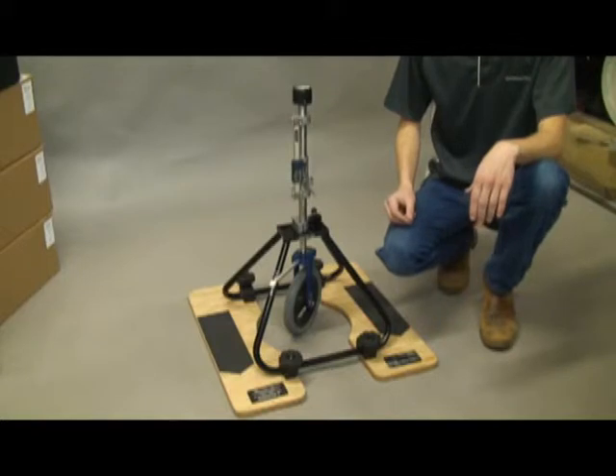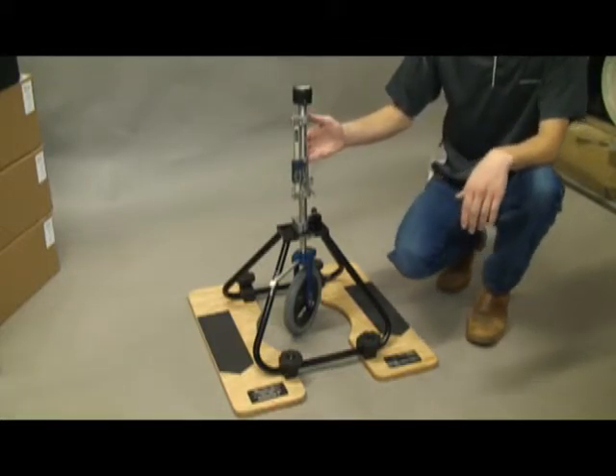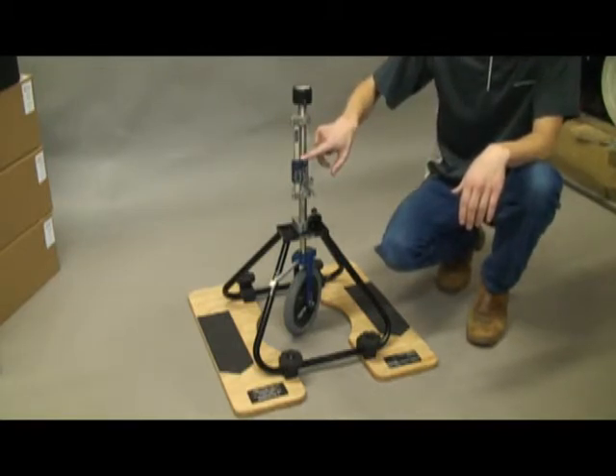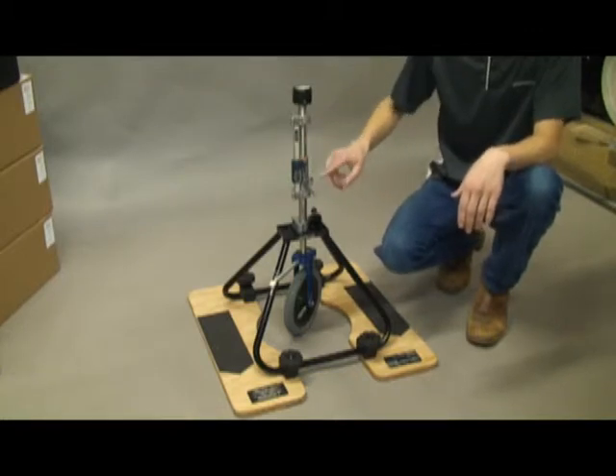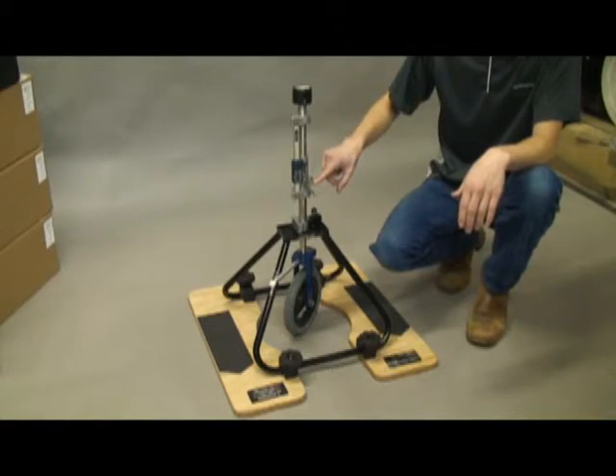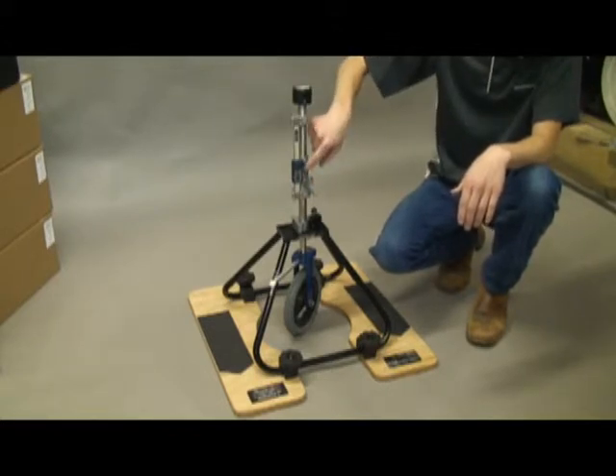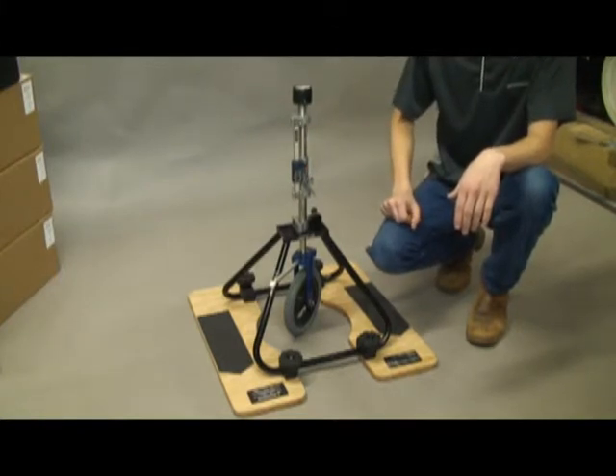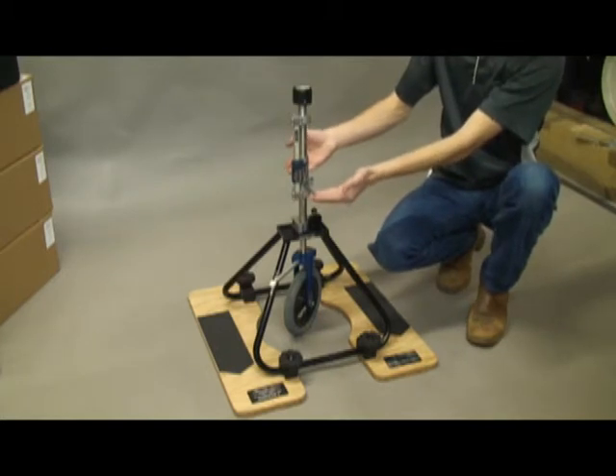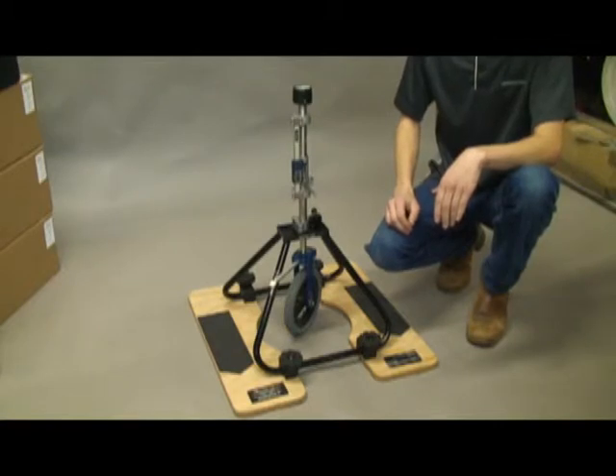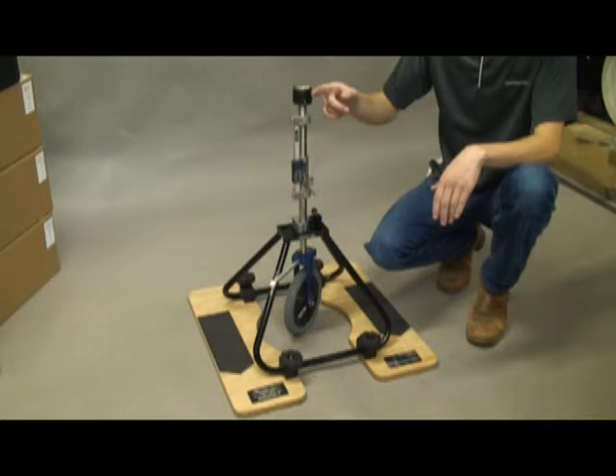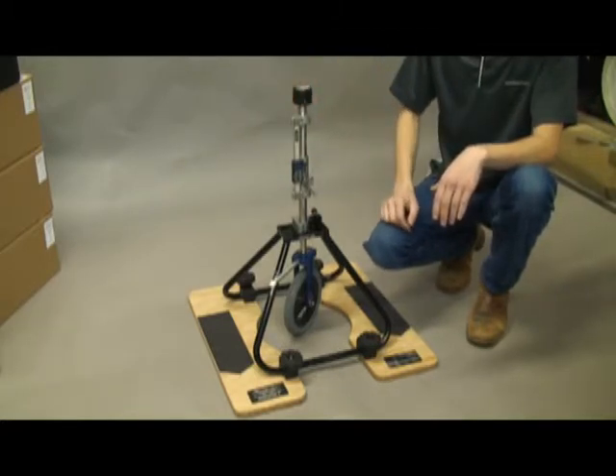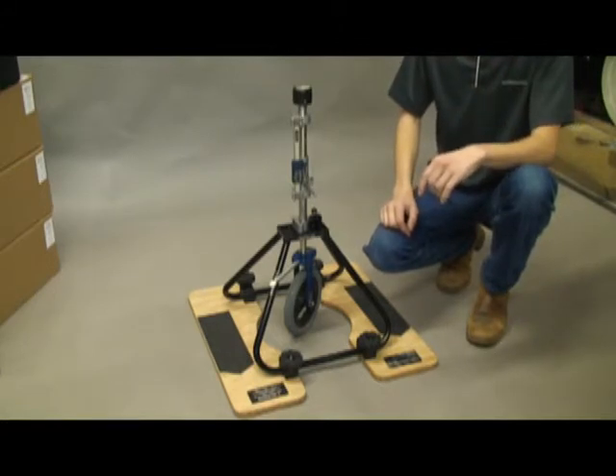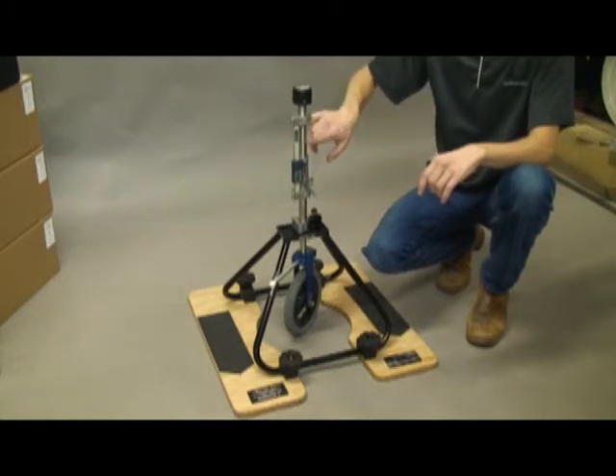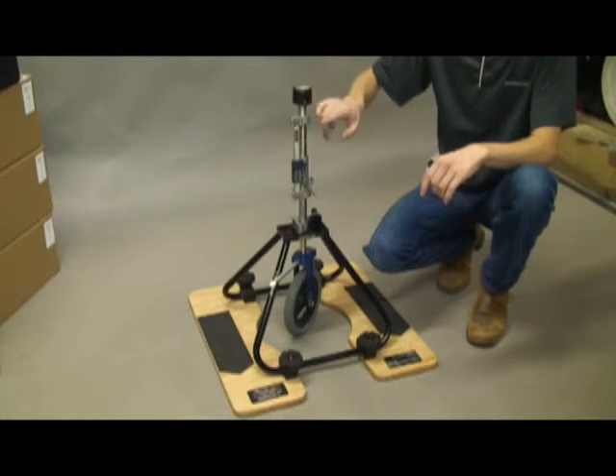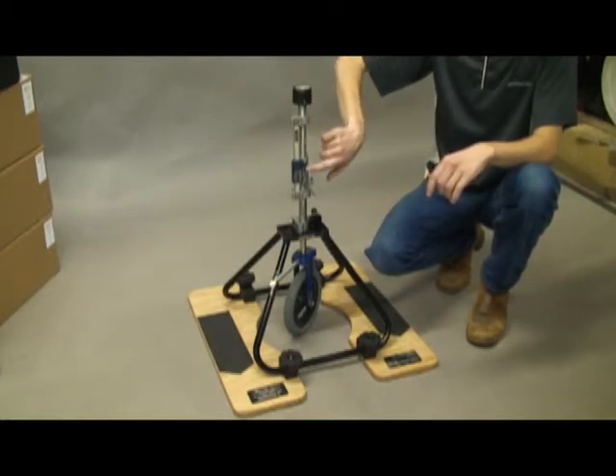The RP spring assembly consists of the following parts: the caliper, which measures the amount of vertical displacement of the indenter; the caliper fork, which follows the spring loading handle as it moves up and down the caliper; the spring, which applies a precision load to the indenter; the spring loading handle, used to lock and load or unload the spring for measurement of firmness and stability. The calibration block provides a place to lift and lower the penetrator assembly, contains the calibration screw, and retains the spring. The outer spring housing contains the calibrated spring inside with the calibration block at the top, with slots on the side for the spring loading handle to lock, load, and unload the spring.